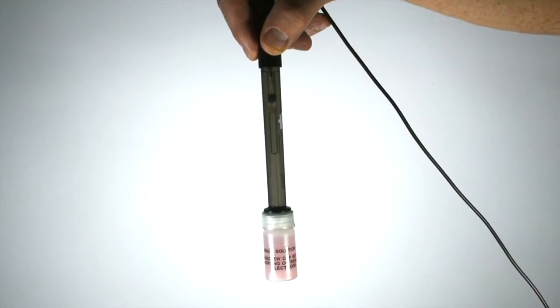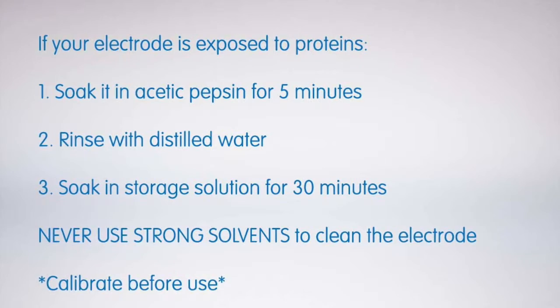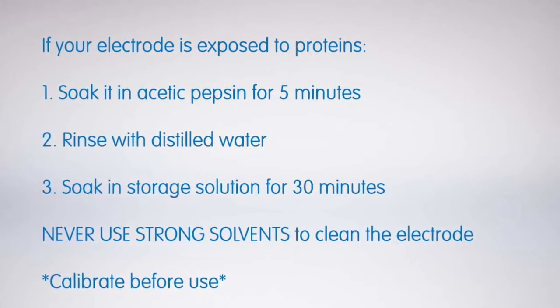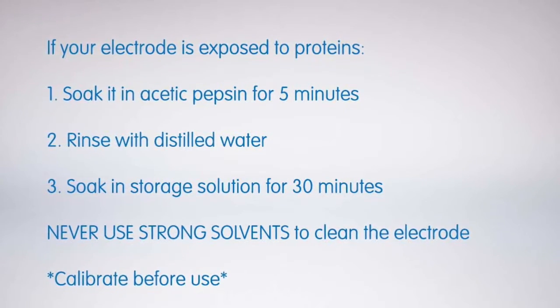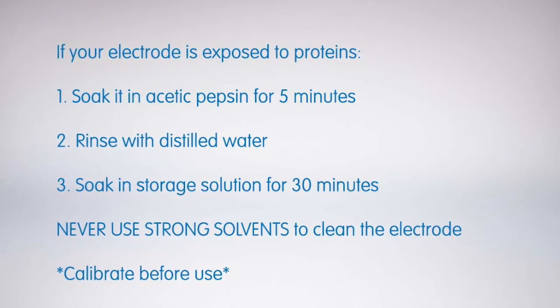After cleaning, let the electrode soak in its storage solution for at least half an hour. If your electrode is exposed to proteins, soak it in acidic pepsin for 5 minutes. Rinse with distilled water. Then soak in storage solution for at least half an hour.